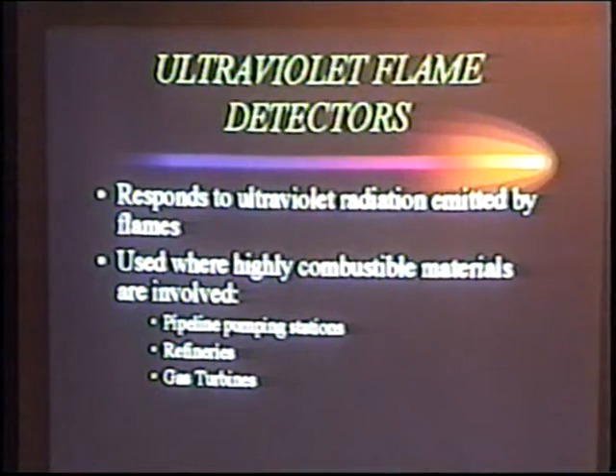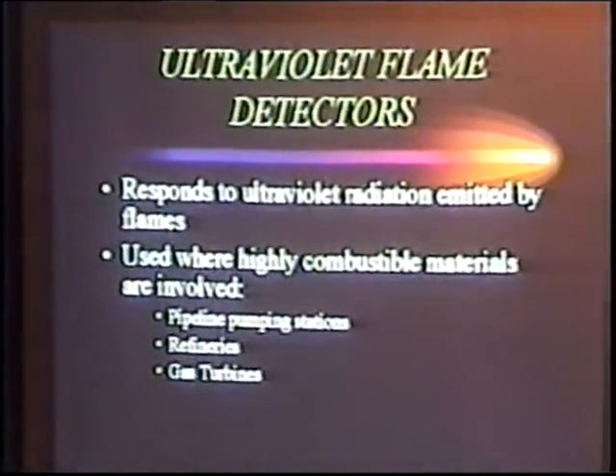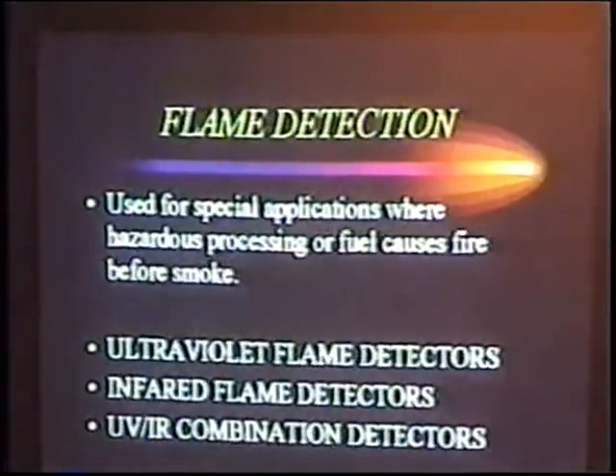Ultraviolet flame detectors do exactly what the name says. They respond to the ultraviolet radiation emitted by flames. This is a very, very fast response type of detector. It's usually used where highly combustible materials are involved. A lot of you here install a lot of these, in refineries, pipeline pumping stations, gas turbines. We use a UV flame detector for a very fast response.